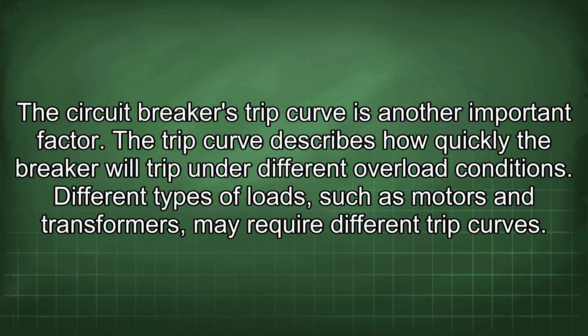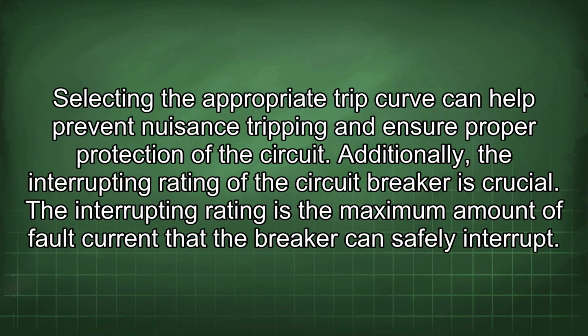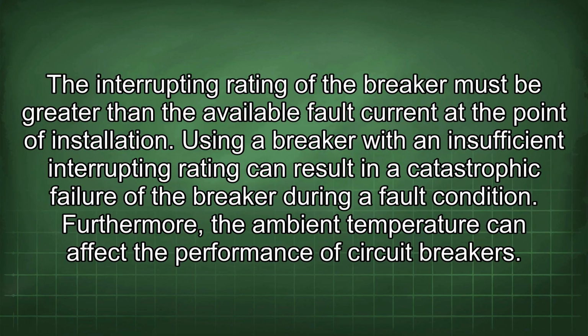Different types of loads, such as motors and transformers, may require different trip curves. Selecting the appropriate trip curve can help prevent nuisance tripping and ensure proper protection of the circuit. Additionally, the interrupting rating of the circuit breaker is crucial. The interrupting rating is the maximum amount of fault current that the breaker can safely interrupt. The interrupting rating of the breaker must be greater than the available fault current at the point of installation.